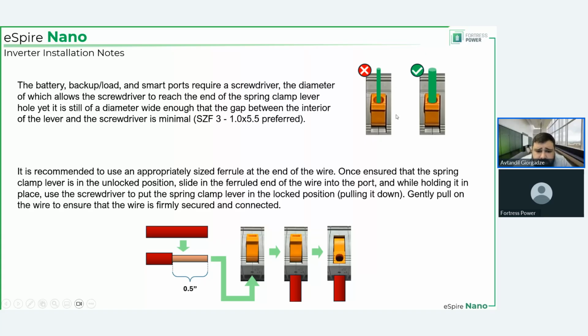Now, as far as how to use the conductor in there, the conductor must have its insulation removed by about 0.5 inches. Then that conductor is placed within the bottom of the port, and then the clamp is closed. One more thing, when you are opening or closing it, initially it will arrive in neutral position. In neutral position, it moves up and down. But if you're closing it, once it moves down, there's one more step. It needs to click in place, right? And when you're opening it, you lift it up, it clicks, and then it's in neutral position. From neutral position, you need to put it in the actual open position. So that's another step that you need to do.